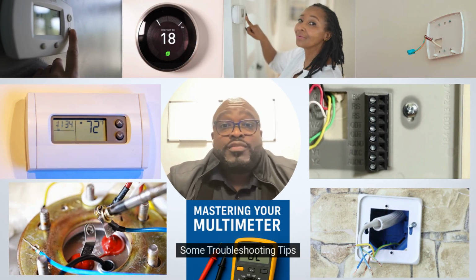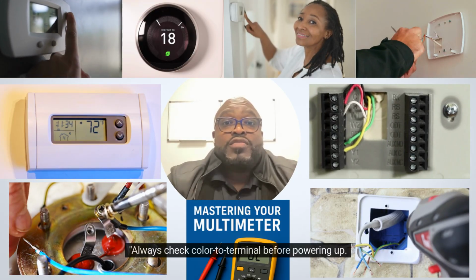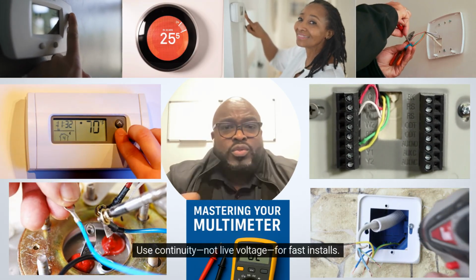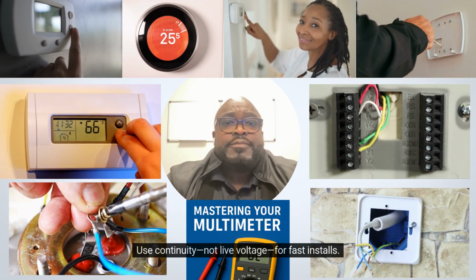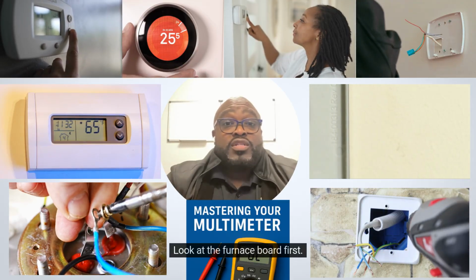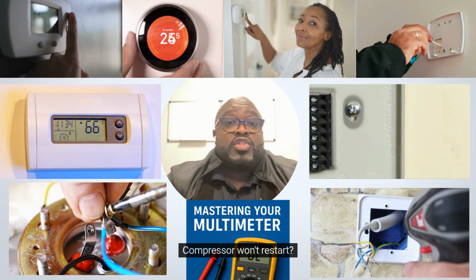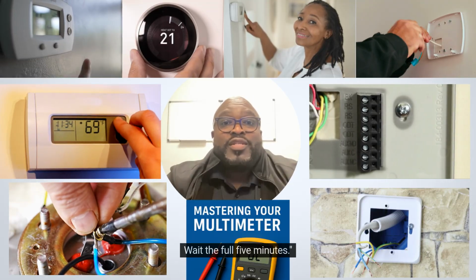Some troubleshooting tips. Always check color to terminal before powering up. Use continuity, not live voltage, for fast installs. No blower in heat mode? Look at the furnace board first. Compressor won't restart? Wait the full 5 minutes.